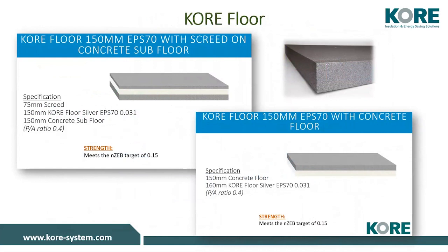Just a couple of U-value examples, two typical scenarios we see very regularly. The example on the left is a screed, insulation, and then a concrete subfloor. If we use an EPS, like our EPS 70 silver, we're using 150 millimeters typically in a floor build-up to get to our U-value target of 0.15 with underfloor heating, based on a perimeter area ratio of 0.4. If we're looking at concrete straight onto insulation and then onto a stone base, probably around 160 millimeters of our silver EPS will get us to that same U-value requirement.